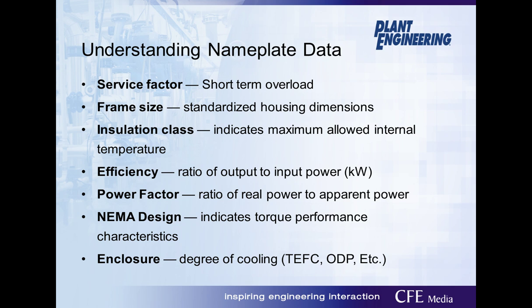Making sure you have the correct enclosures can play a key part in cooling for the motor. There are many different types of enclosures, such as TEFC, meaning totally enclosed fan cooled, ODP, meaning open drip proof, or TEAO, meaning totally enclosed air over, as well as many others. Each motor enclosure can be specific to application and to the environment the motor is located in.